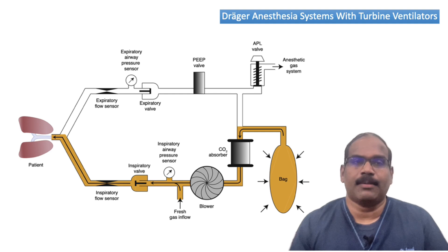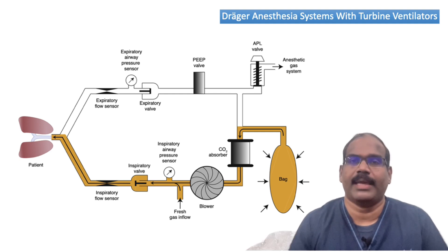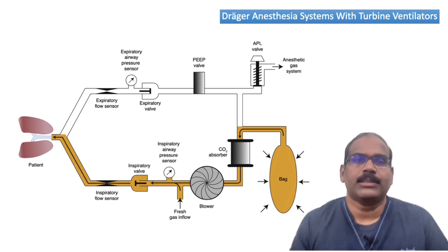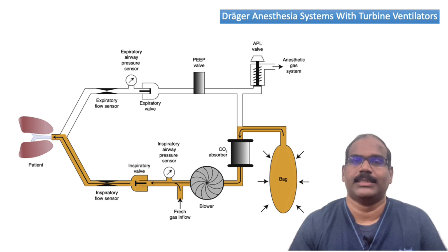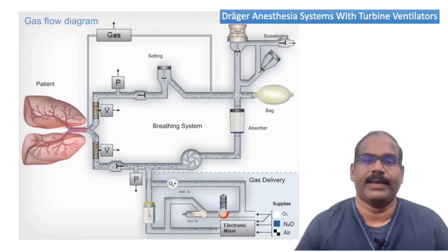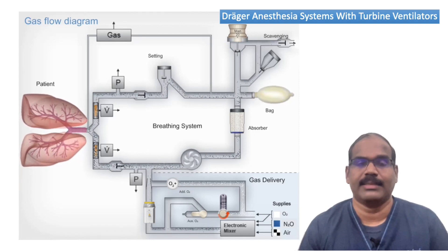Unlike piston ventilators, turbine ventilators are found in some manufacturers such as Draeger. They primarily have a pressure generator. Turbine ventilators use mechanical energy to spin a small turbine or fan at very high speeds to create pressure and flow. Possible functional advantages include better responsiveness to patient triggering, more effective pressure support ventilation, and in some cases more accurate tidal volume delivery under high ventilatory workload. You can see the working principle of turbine ventilators, with the turbine rotating faster during the inspiratory phase, driving gas into the lungs.